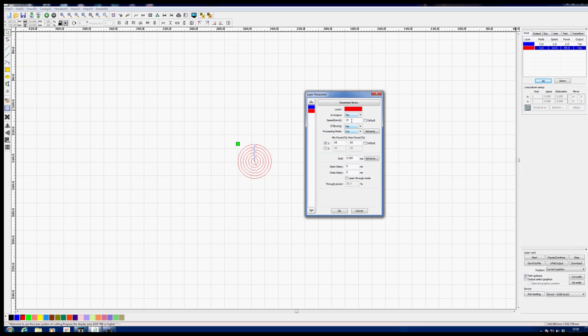So that speed could be set to 7, 14 or 28, depending on which range of power you want to be working in. I'm going to set it to the middle range, 14, which is where I do most of my work. And I'll remind you again, this takes me up to 80 watts without overheating the block.